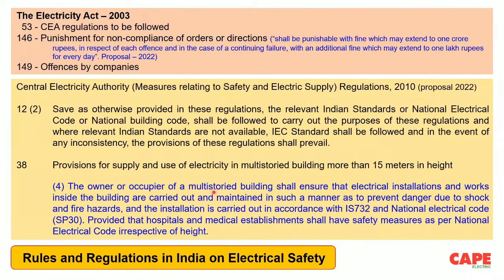Now, coming to the CEA measures relating to safety and electric supply, of course, I am referring to the proposal of 2022. I don't know whether it will be finalized or not, but the same proposals have been there since 2016 or 2018. So, save as otherwise provided in these regulations, the relevant Indian standards and the National Electrical Code or National Building Code shall be followed. Basically, what this says is that whatever is not contained in the regulation, you can refer to the Code of Practice of the Bureau of Indian Standards to achieve safety. That means the regulation is mostly discussing generation, transmission, distribution, and up to the point of commencement of supply. Of course, there are regulations applicable inside the house as well. So whatever subject is not covered in the regulation, you can refer to the Code of Practice.